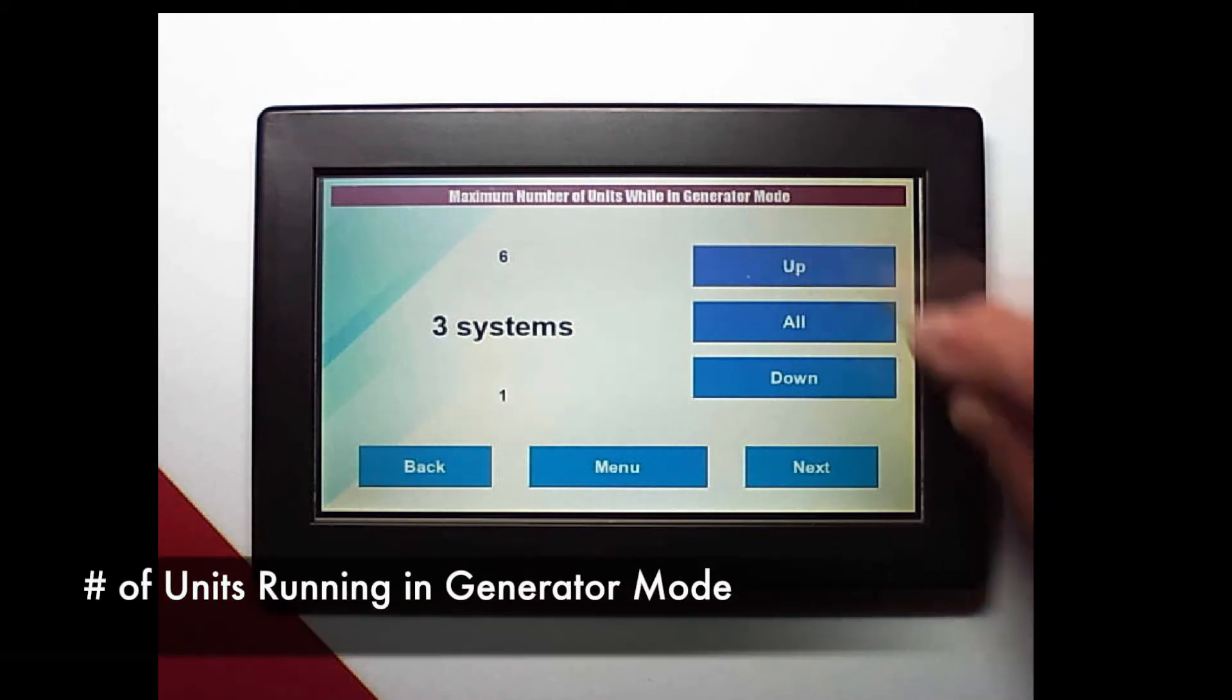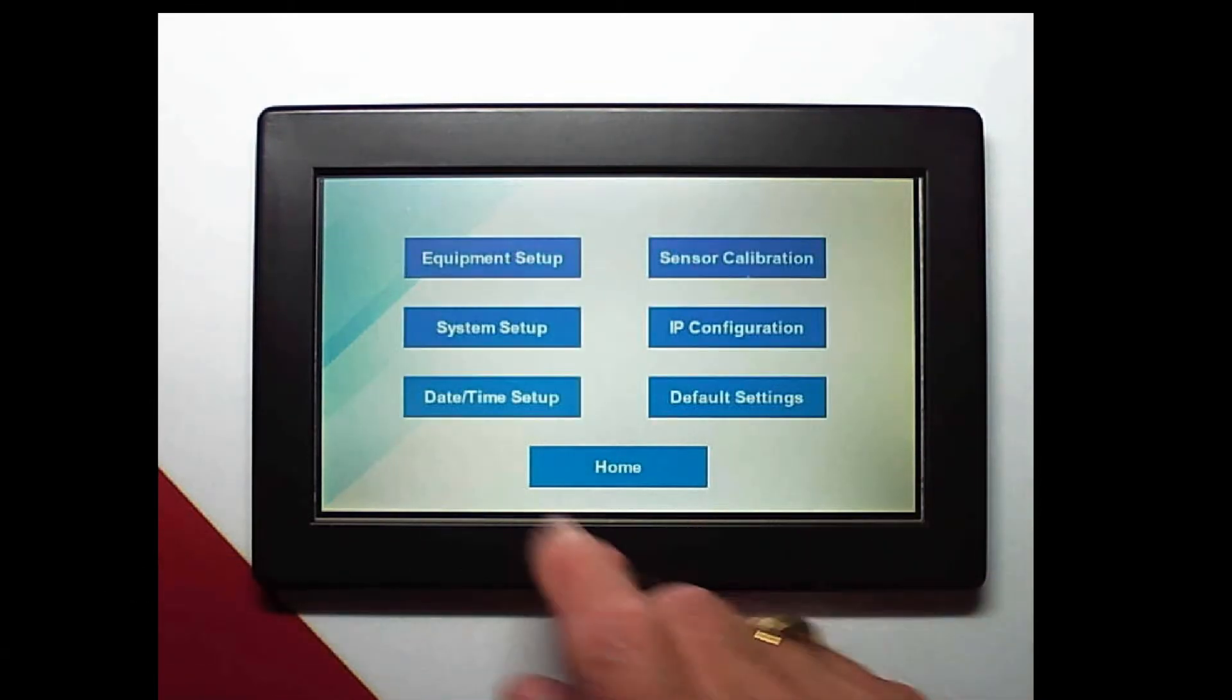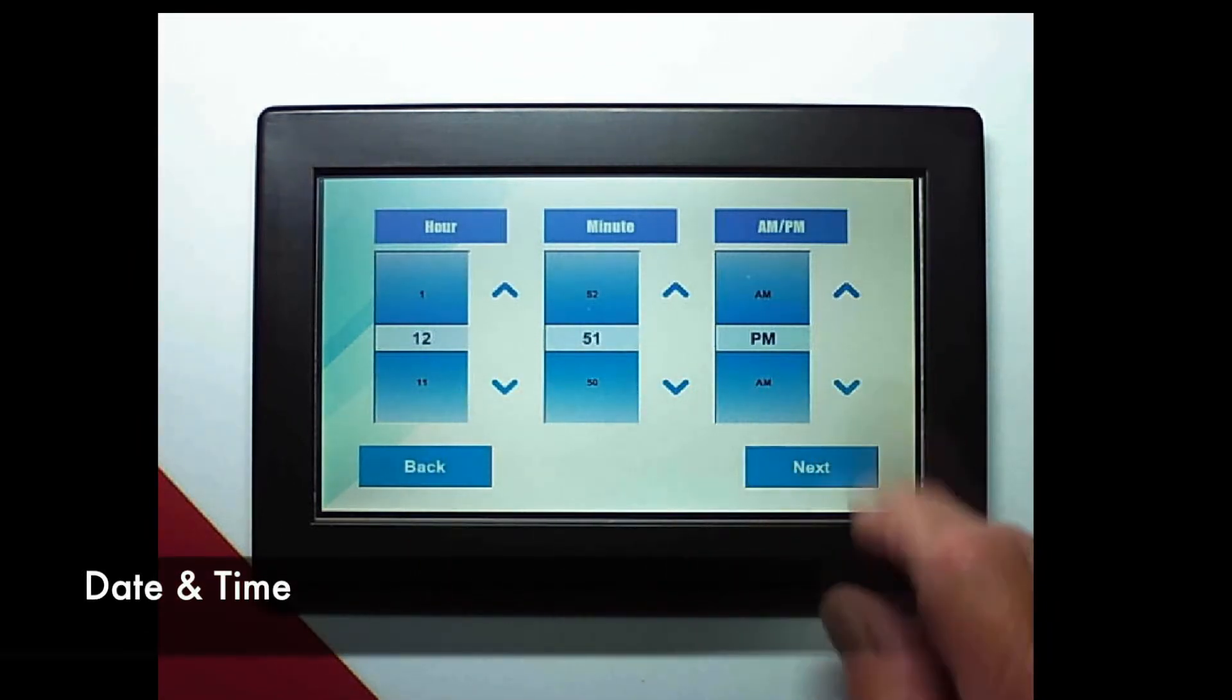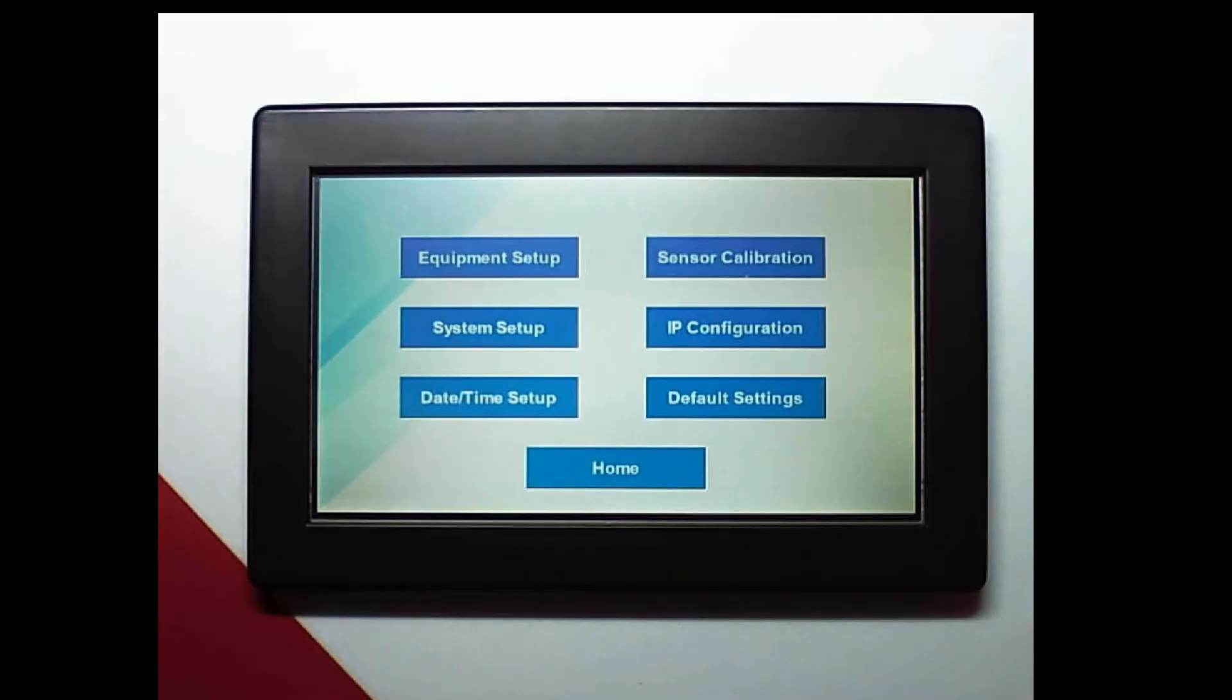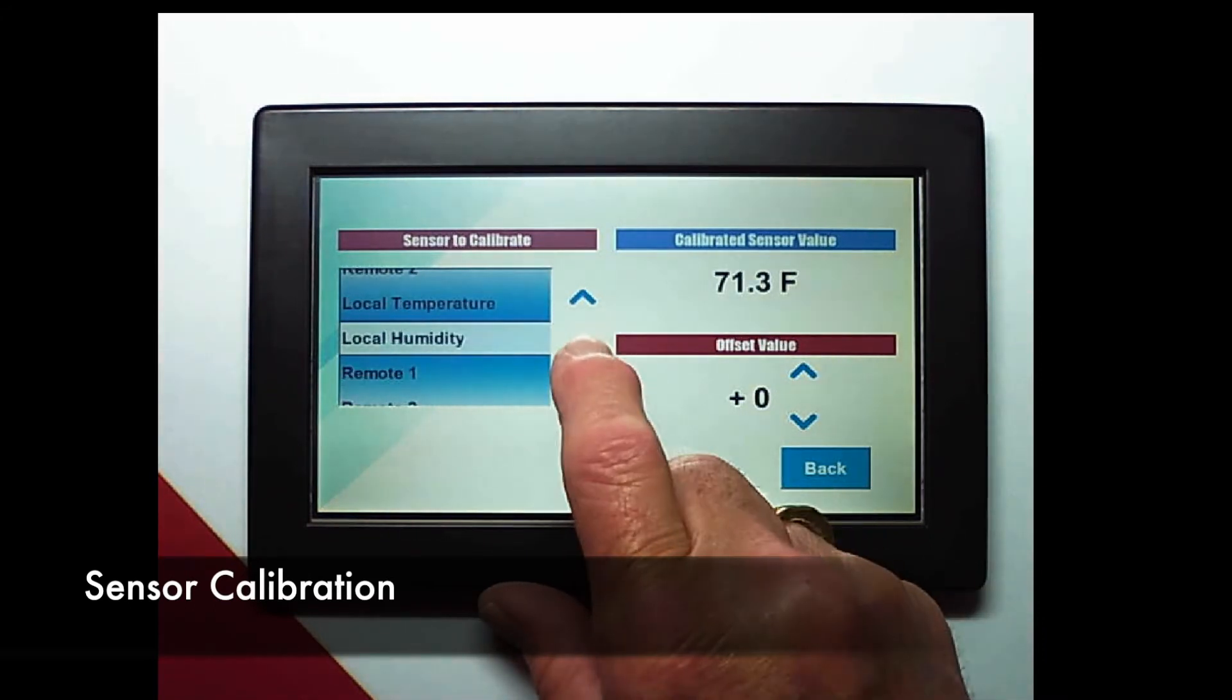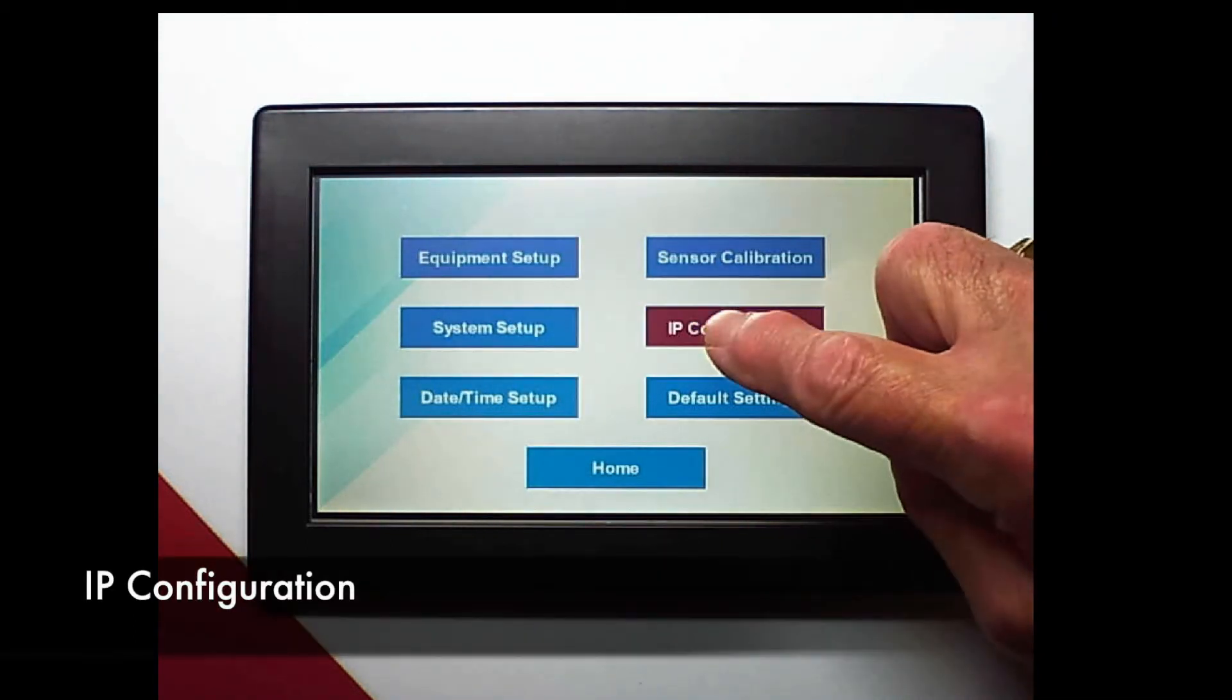How many units are we going to run in generator mode? And this is just our brightness. Next let's look at the date and time. You can see across here we can scroll up and down to change the date and time. We can calibrate any of the sensors connected to the unit by simply scrolling up or down to change the sensor and then on the right scrolling up and down to change the offset.